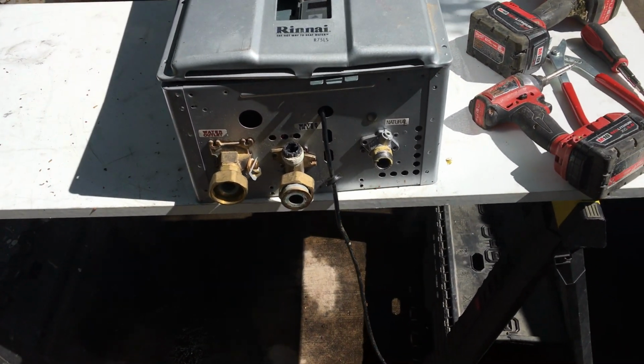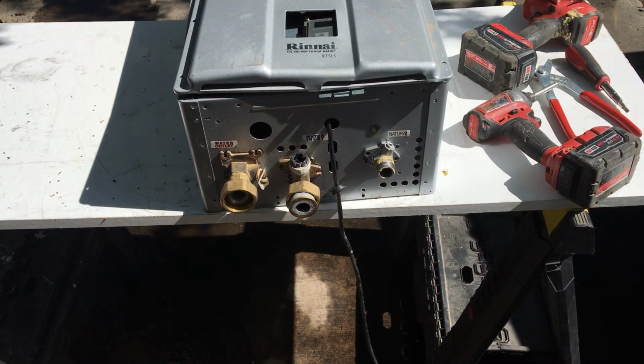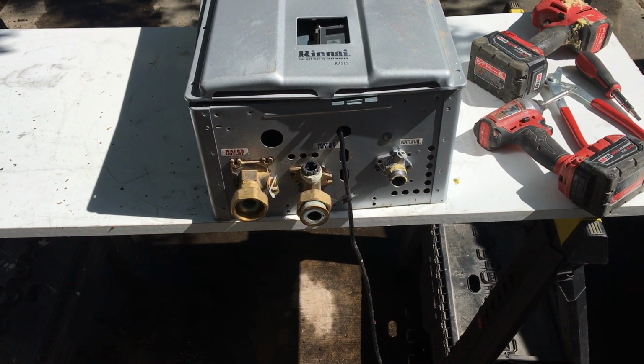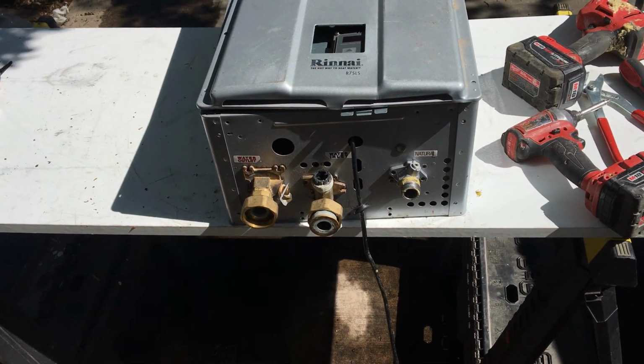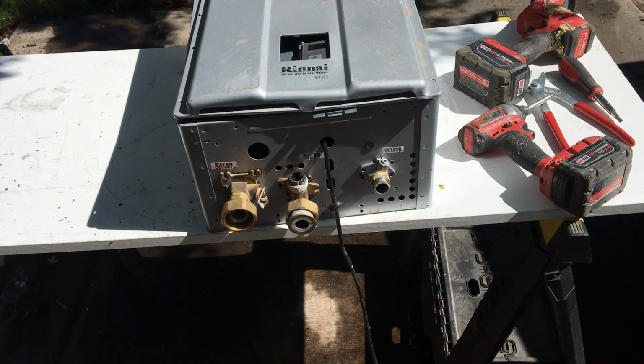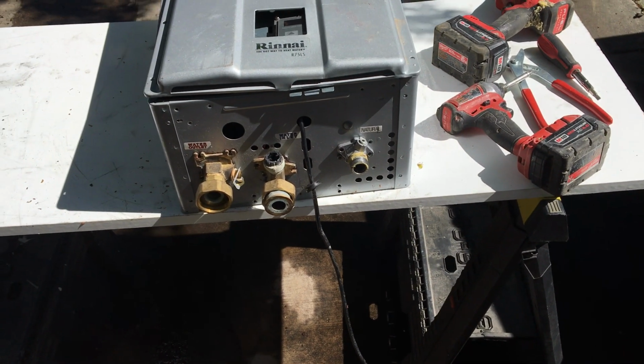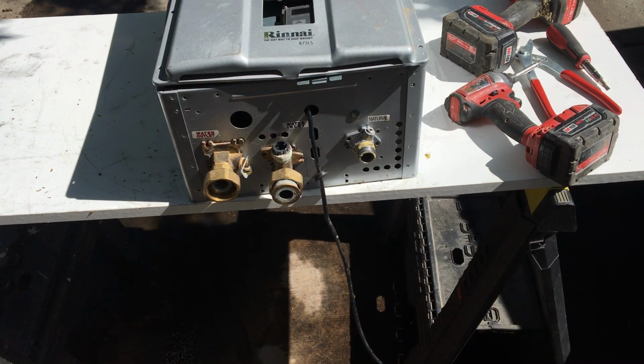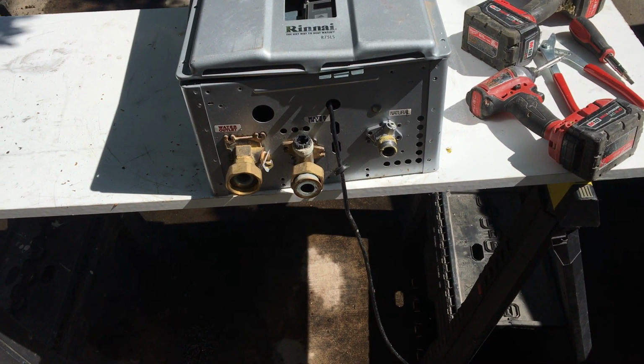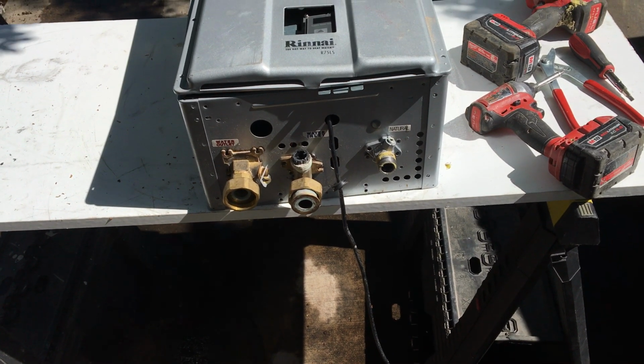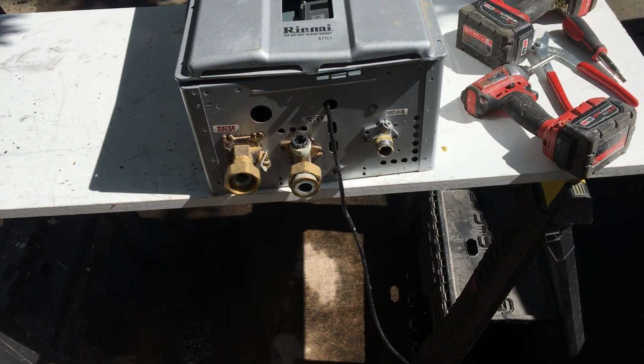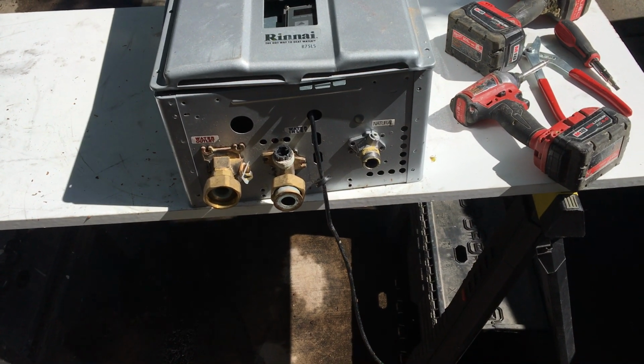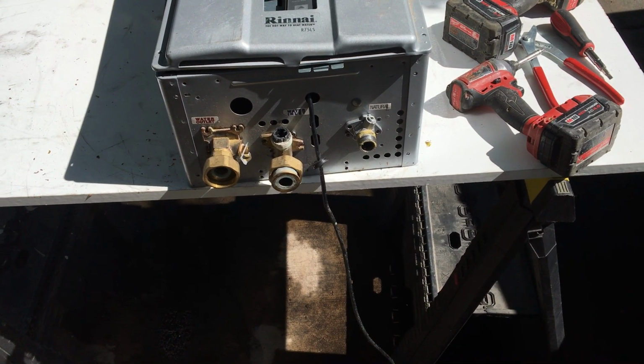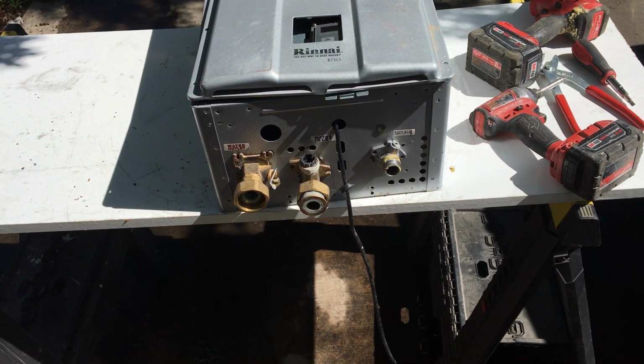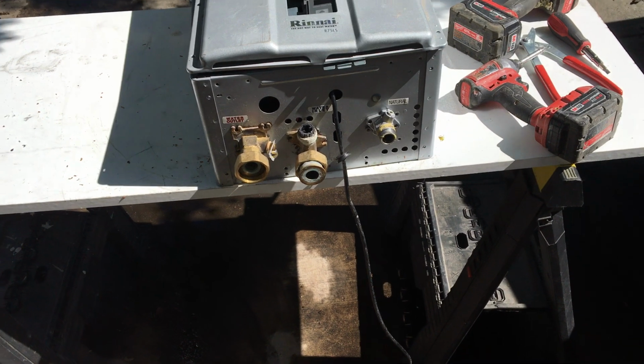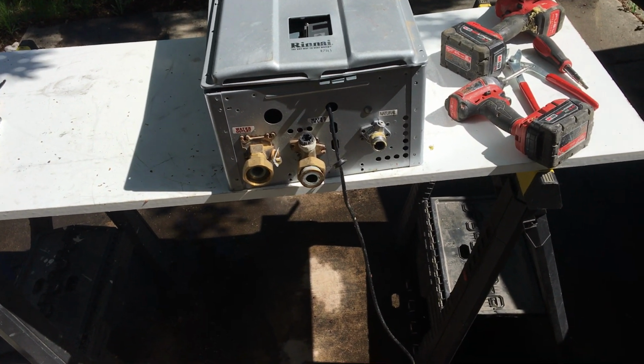So basically, on a tankless water heater, the whole idea is that it heats water as fast as you can run it through there. If it can't keep up with the temperature you have it set at, it just restricts the flow down to the point where it can maintain a particular water temperature. So you'll experience reductions of water flow if you overtax these or get too much water through them. If you can treat them right and learn how to use them, they're probably fine. They'll put out hot water all day if you want, at a limited gallons per minute flow.